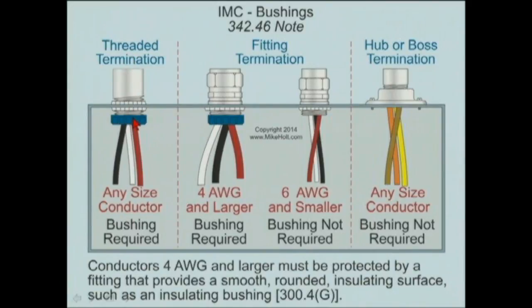So we probably need to clarify that the conduit enters the box right here, right? Well, then you always need what? You need a bushing. Right. These are connectors entering the box, so you comply with 300.4(G) requirements when a connector enters the box. Right. Okay, good point.